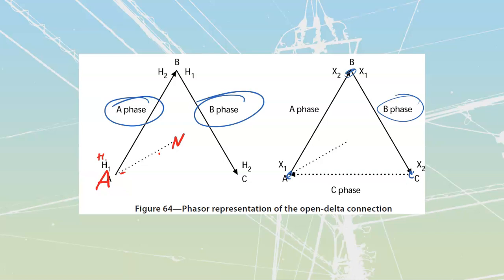It does mean, though, that I'm going to have some weird kVA values for these things. Because when I take a look at it, normally inside of an actual true delta system, I'm going to have two currents that combine to form one supercurrent. We call that supercurrent the line current, and we call these two smaller currents the phase current. But I don't have that option when I'm looking at open delta.